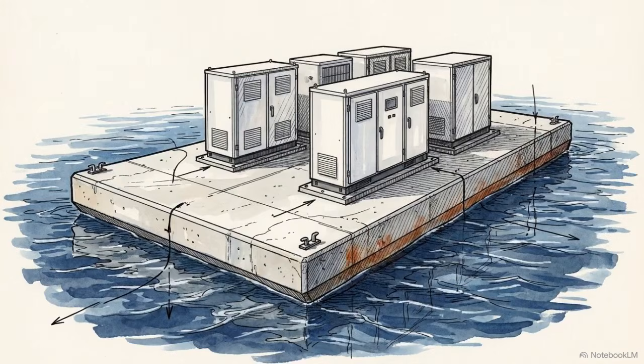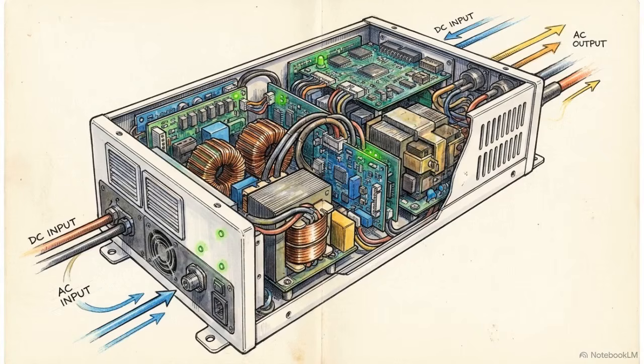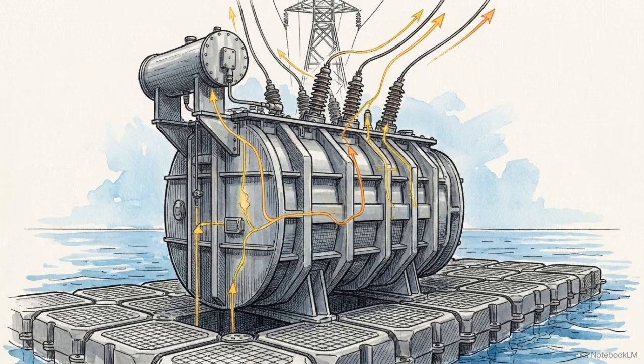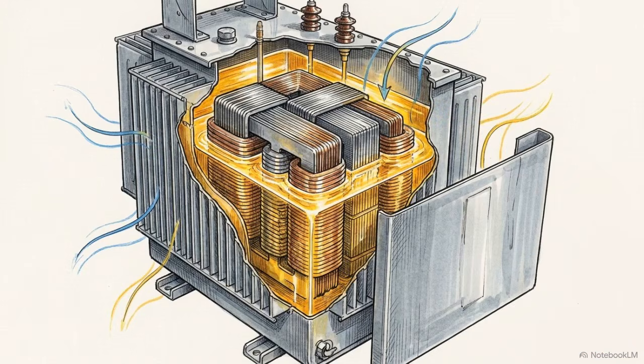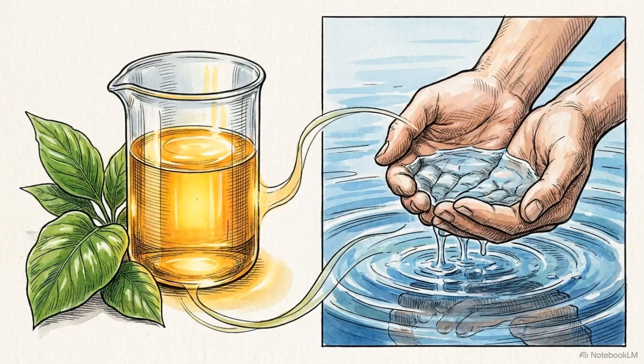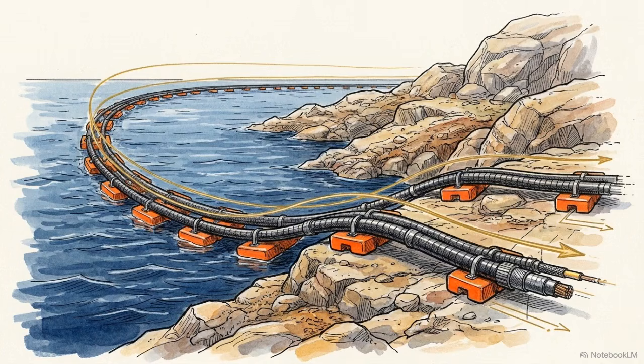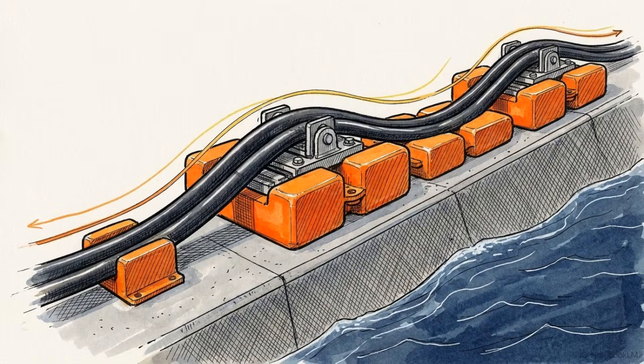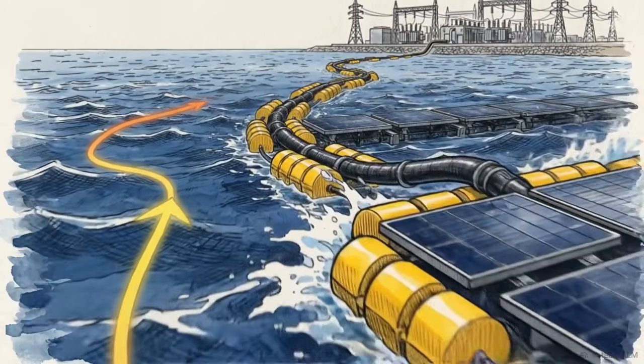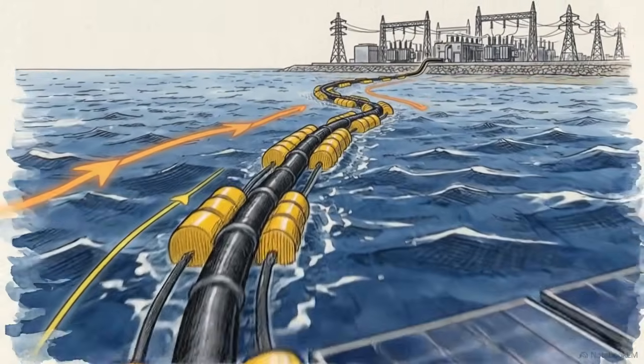From there, the consolidated power travels to massive floating inverter stations, 60-ton platforms constructed from ultra-light ferro-cement. Inside these floating stations, the inverters convert the DC electricity into alternating current. The power is then stepped up in voltage by floating transformers. Crucially, these transformers are filled with natural ester oils, entirely eliminating the risk of toxic chemical spills in the local water supply. To move this high-voltage AC power to the mainland grid, the final connection utilizes a flexible catenary cable loop. This loop rides on specialized floats, self-adjusting to bridge the physical gap between the moving water and the solid shoreline. This unbroken, heavily armored electrical highway maintains absolute isolation from the surrounding water, safely delivering grid-scale power from an actively shifting platform.